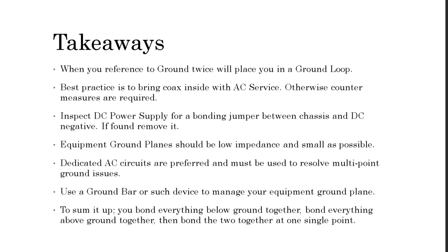Okay, takeaways. When you reference to earth ground twice, you will place yourself in a ground loop every time. Best practice is to bring your coax inside with your AC service. Otherwise, countermeasures are required. Inspect your DC power supply for a bonding jumper between the chassis and DC negative. If you find it, remove it.